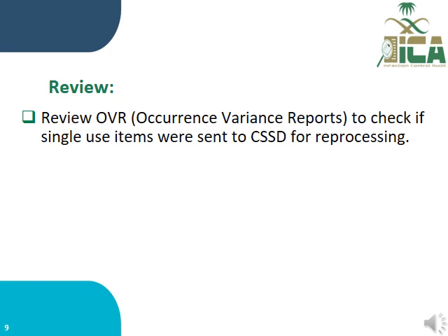You also need to ask for and review the OVR, occurrence variance report, to check if any single-use items were sent to the CSSD for reprocessing. You can ask infection control about any OVR that mentions reprocessing of single-use items, or that they were already sent to the CSSD for reprocessing.